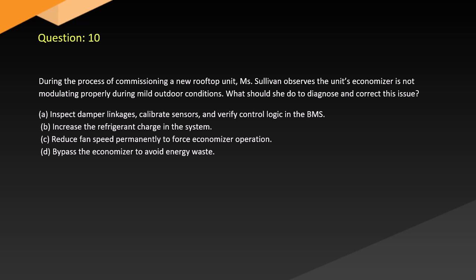Question 10. During the process of commissioning a new rooftop unit, Sullivan observes the unit's economizer is not modulating properly during mild outdoor conditions. What should she do to diagnose and correct this issue? A. Inspect damper linkages, calibrate sensors, and verify control logic in the BMS. B. Increase the refrigerant charge in the system. C. Reduce fan speed permanently to force economizer operation. D. Bypass the economizer to avoid energy waste.